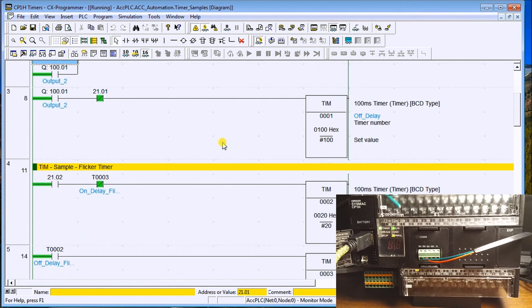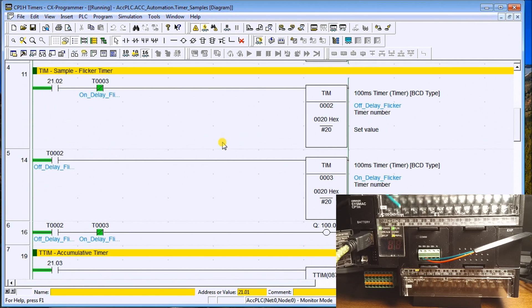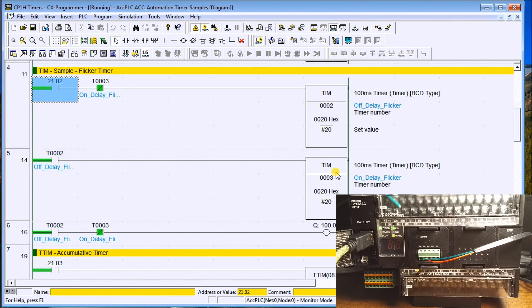The next timer is a flicker timer, which cycles something on and off repeatedly — on for a period, then off, then on again. When I energize the internal contact bit it passes through the normally-closed contact of Timer 3 and energizes Timer 2. When Timer 2 expires it energizes Timer 3; Timer 3 expires and opens that contact, resetting the whole thing and starting over. The actual output is Timer 2 AND NOT Timer 3, which drives Output 3.